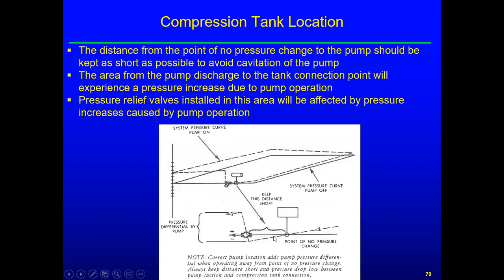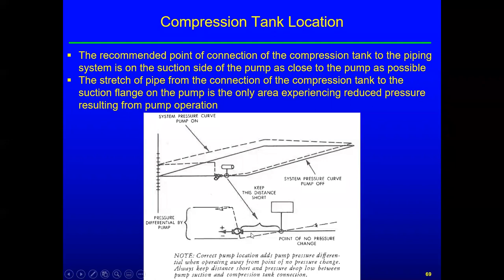into the pump. Did that thing change? That daggone slide. It's just touchpad, it's touchy. Okay, so that water is being sucked. You know, the lowest pressure is at the eye of the impeller, okay? Because that's what that pump does. It establishes really low pressure, and then it flings that water to the outside and the pressure jumps up. You got velocity and pressure, and then you slow it down and you get more. The velocity turns into more pressure, okay? So the lowest pressure point in the whole system is right here at the eye of the impeller or the suction flange. It doesn't really matter much.